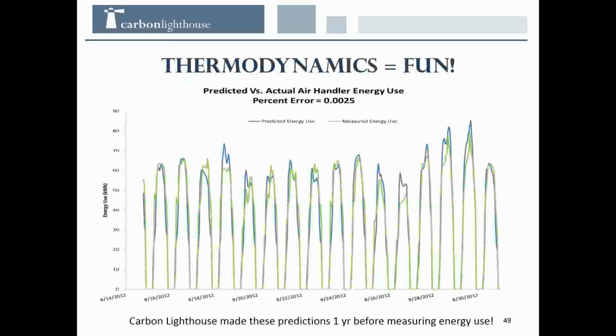This is entirely enabled by getting data. To make these predictions, we measure temperatures in return air, outside air, and mixed air. We measure electrical current, voltage, and power factor going through compressors and fans. We measure all sorts of things, and we do an awful lot of regressions to figure out how all these factors play together so we can make predictions.